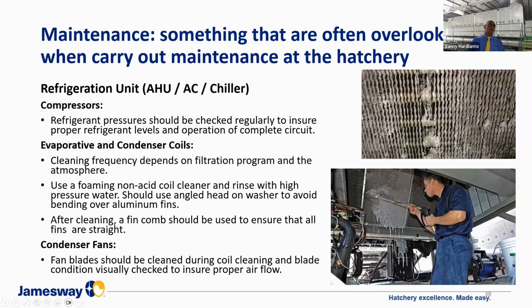The condenser fan blades also need to be cleaned during maintenance. Removing the dirt on the fan blades can keep a good air suction to remove the heat from the condenser, and it will affect the cooling power of the unit itself.